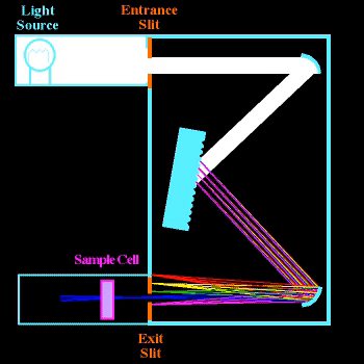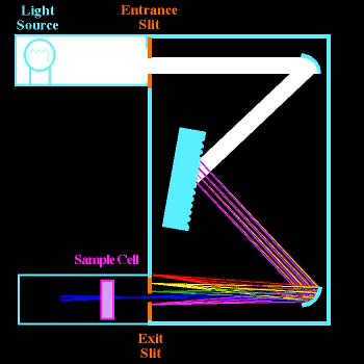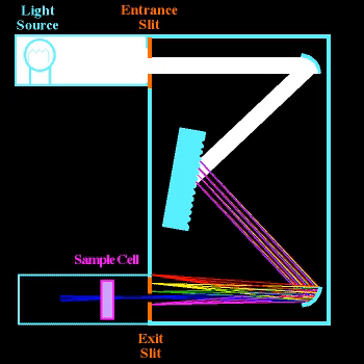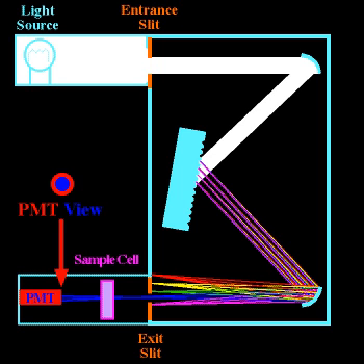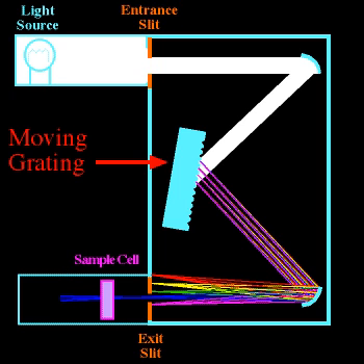When the monochromator is tuned to the blue wavelength, say 425 nanometers, the blue light rays are focused onto the slit itself and all other wavelengths strike the inside wall and are absorbed. This is why monochromators are internally painted black, to absorb unwanted and scattered light inside the cavity. The photomultiplier tube, or PMT, sees only blue light that passes through the sample cell from the monochromator.